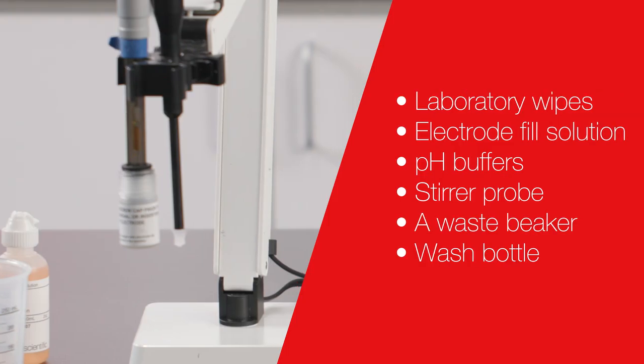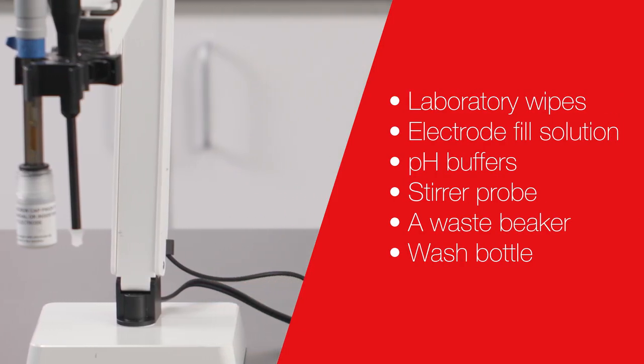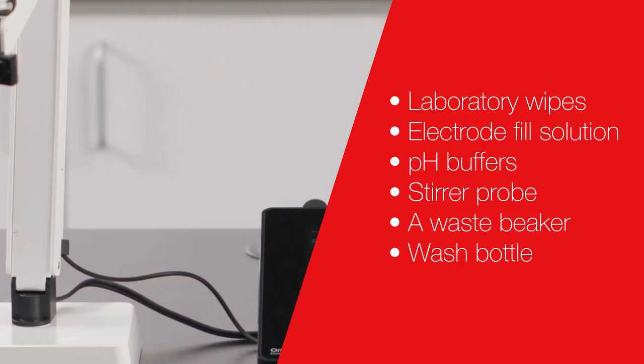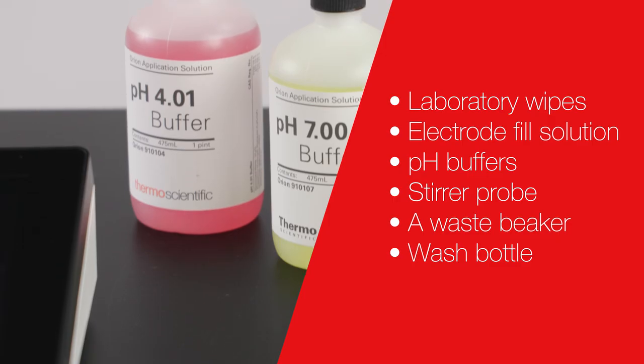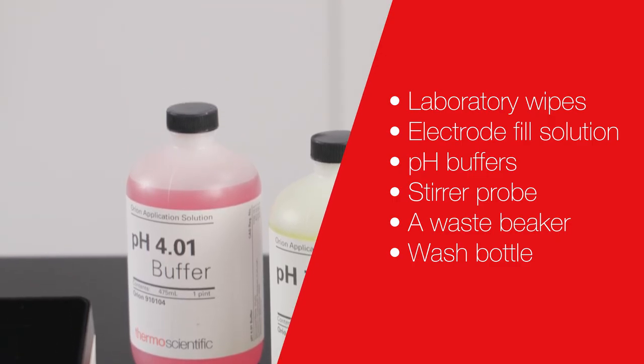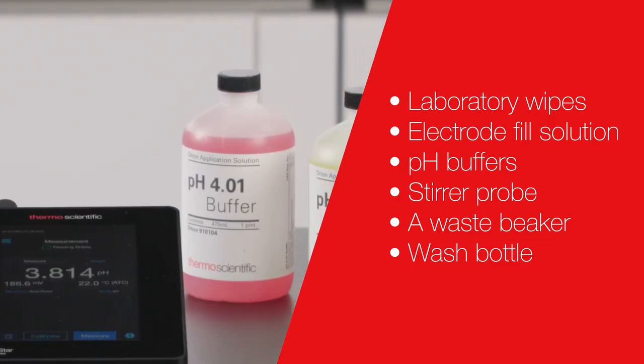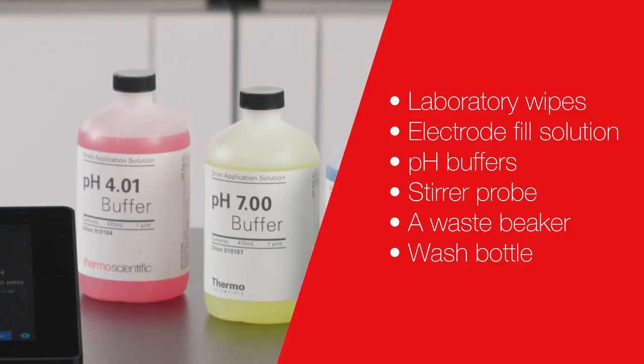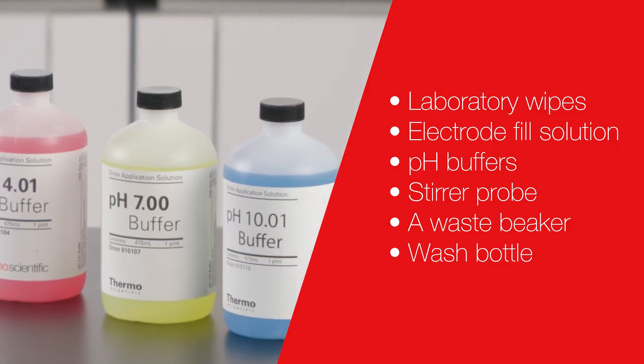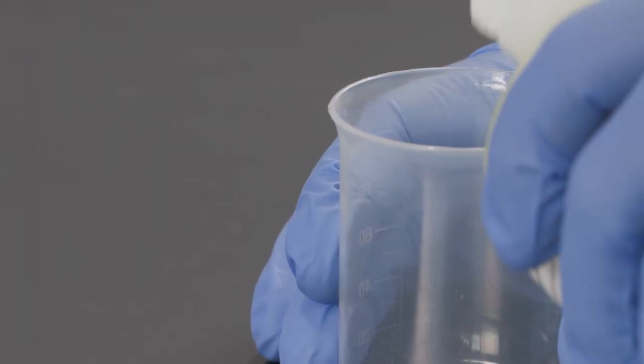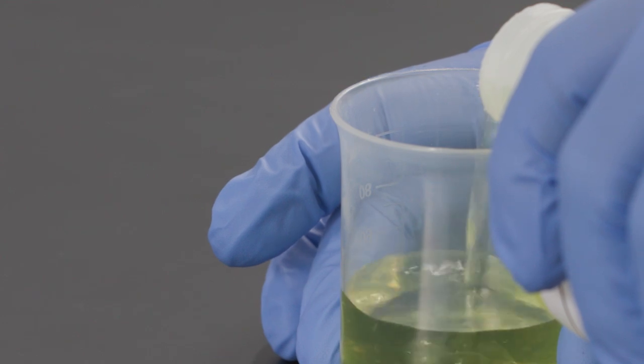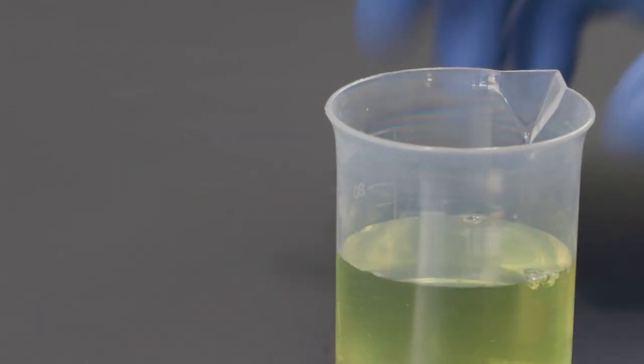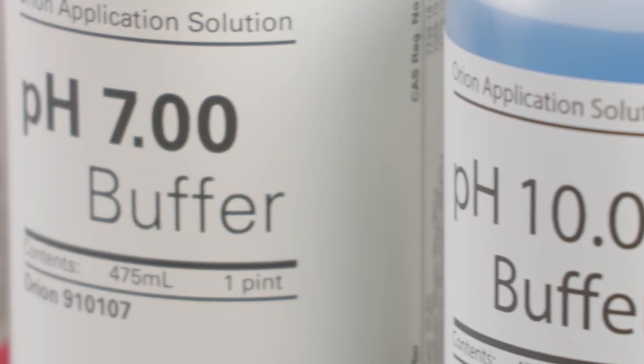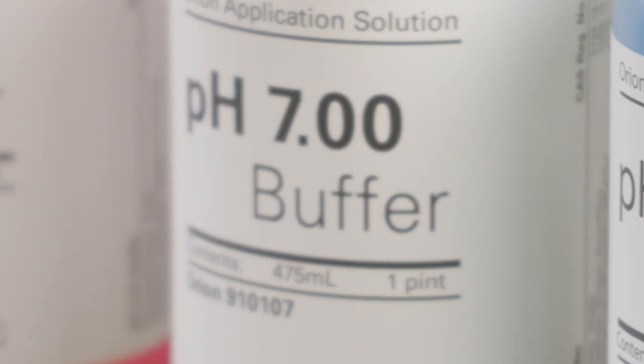We'll also need to gather the right supplies: laboratory wipes, electrode fill solution, pH buffers at 4, 7, and 10 pH, a stirrer probe, a waste beaker, and a wash bottle of purified water. For a good, valid calibration, it's important to avoid reusing buffers. Always use fresh pours of unexpired buffers. Single-use buffer pouches or 60 milliliter bottles are also good options.